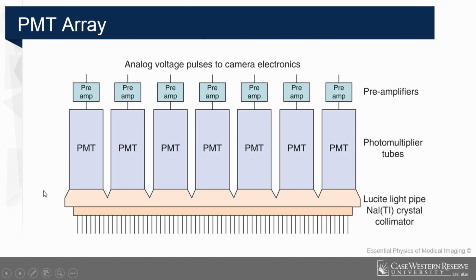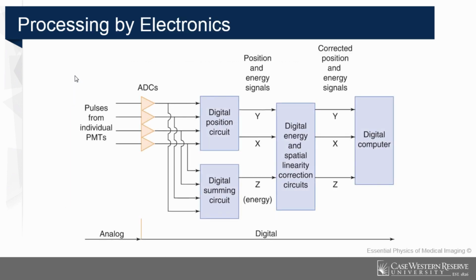So here is what I just talked about. First you have a collimator in front of the patient. Next you put the scintillation crystal next to it, and very next are those PMTs. They have their size, but they are packed behind the crystal detector. Then after amplification from this array of dynodes, you have an electrical signal which goes through pre-amplification for further use. Here is the further processing.